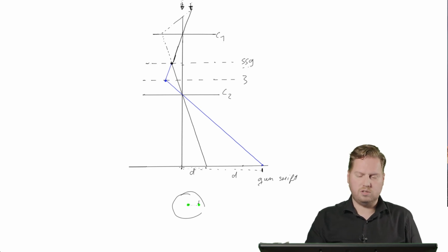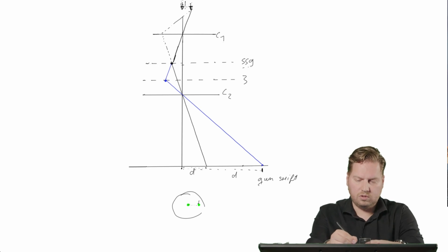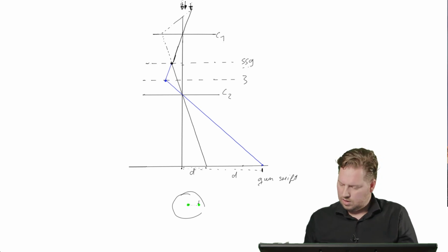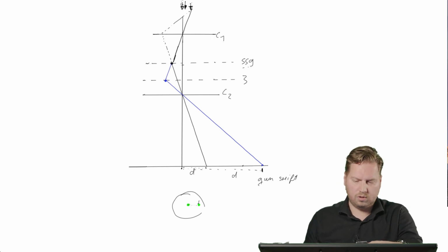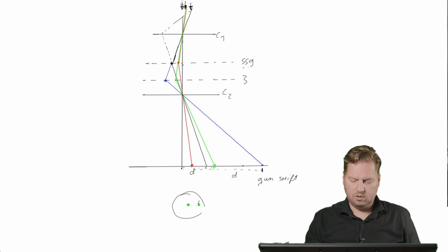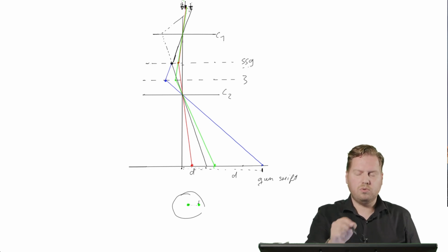And then you are in a better situation, because then the gun has been moved closer to the optical axis. Let's then take again a different color. So we're now closer to the optical axis. So now the situation is like this. So if we go down here, like so, spot size 9, and through the center, we end up here. And with spot size 3, so you have improved if you take spot size 9 and it's very, very bad, and you use gun shift to bring this back to the center, then you have improved the situation.